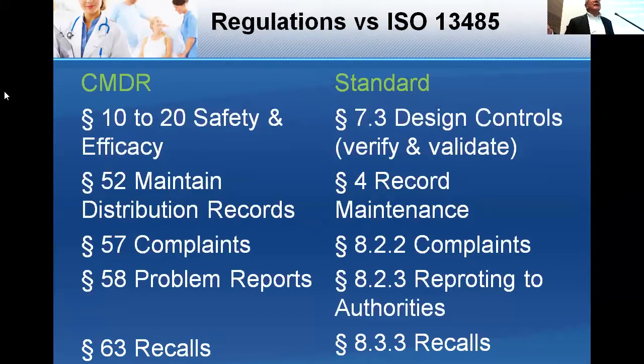You've got a very tight linkage there, so make sure your procedure considers both the standard and the regulations in the countries where you're marketing your products, because you may have to make some tweaks. For instance, in Canada we have 10 days to make a mandatory problem report; in the US, you have 5 days. So make sure your procedure recognizes the difference between countries.